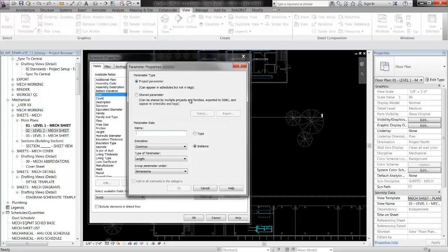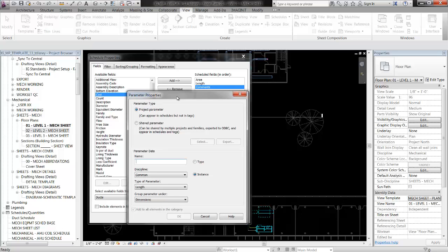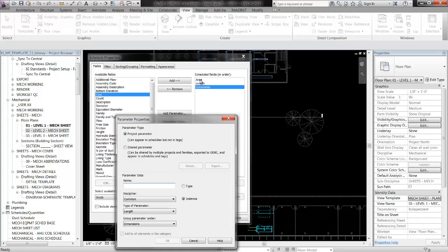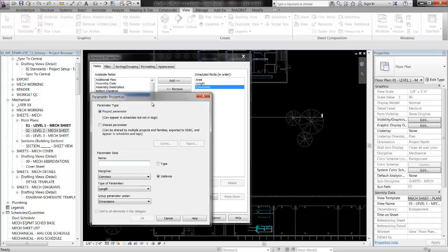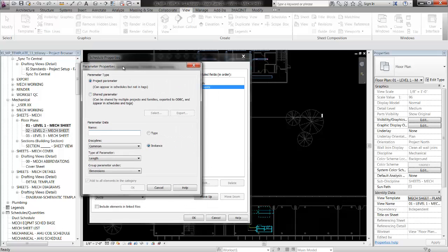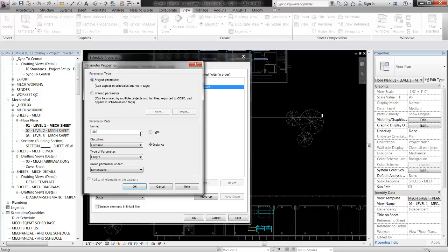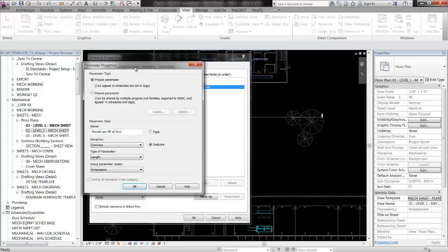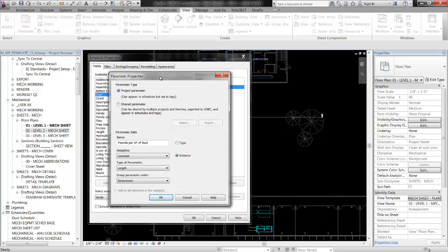Let's add a parameter — the parameter we need is the pounds per square foot of duct, because we have area here. If you know pounds per square foot, we can calculate how much a piece of duct weighs. For this video I'm just going to use a project parameter and call it 'pounds per square foot of duct.' Revit is fairly picky about units, so you have to make sure your units match up, otherwise it will give you an error. Try to make the units work out.